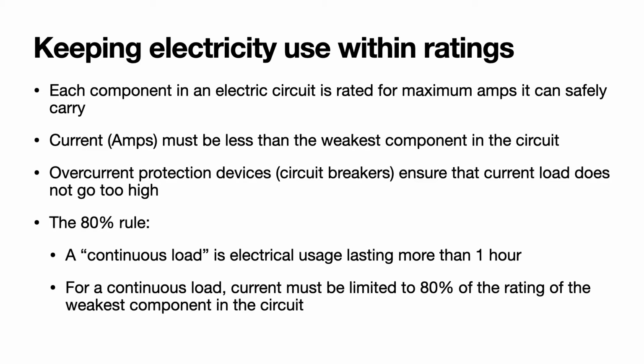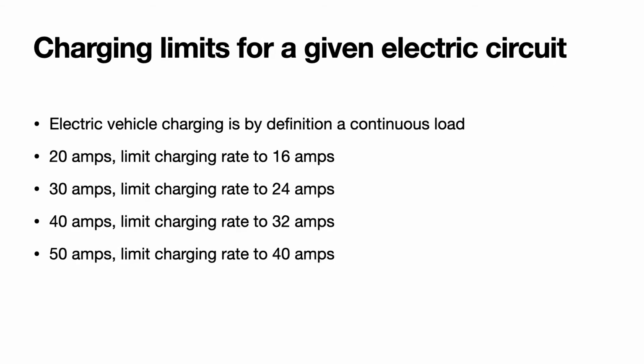Another issue that applies to electric vehicle charging is what's called a continuous load. A continuous load is electricity usage that lasts for more than an hour. When you have a continuous load situation, the current must be limited to 80% of the rating of the weakest component in the circuit. Electric vehicle charging is a continuous load because it usually lasts for more than an hour. So that means if we have a 20 amp circuit, we must limit the charging rate to 16 amps. If we have a 30 amp circuit, limit it to 24 amps, and so on, as you see in this table.